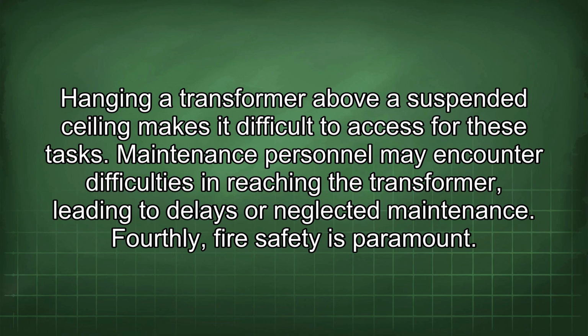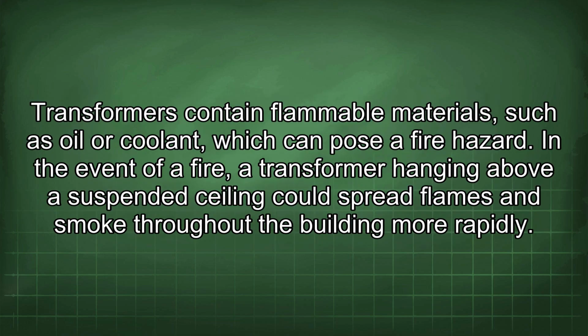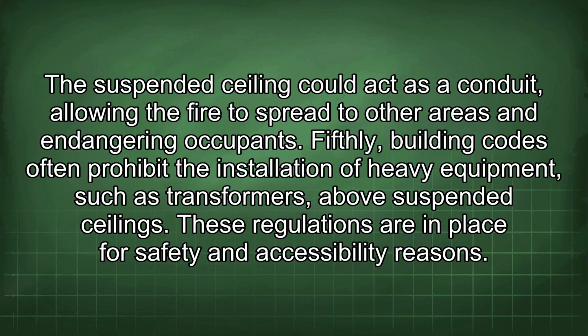Fourthly, fire safety is paramount. Transformers contain flammable materials such as oil or coolant, which can pose a fire hazard. In the event of a fire, a transformer hanging above a suspended ceiling could spread flames and smoke throughout the building more rapidly. The suspended ceiling could act as a conduit, allowing the fire to spread to other areas and endangering occupants. Fifthly, building codes often prohibit the installation of heavy equipment such as transformers above suspended ceilings.